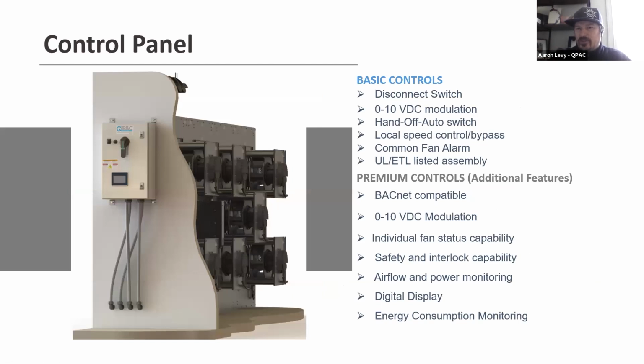We offer 2 sets of controls, basic and premium. 95% of the jobs we sell are premium controls because of the BACnet capability, the 0 to 10 modulation, which is also the same for the basic controller. But you get individual fan statuses, safety and interlock capabilities for start stop. You get airflow and power monitoring, a touchscreen digital display, energy consumption monitoring. So you can check in on every little component of that system.